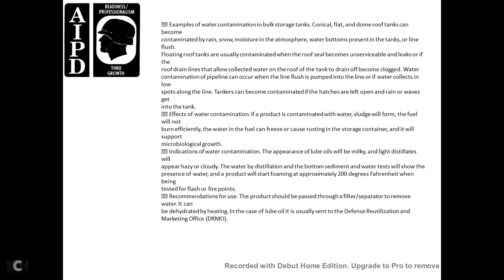Water contamination in pipelines can occur when the line is flushed and pumped with water which collects in low spots along the tank line. Tankers can be contaminated if hatches are left open to rain and waves. Effects of water contamination: product contaminated with water will form sludge, fuel will not burn efficiently, water in fuel can freeze causing rusting of storage containers, and it will support microbiological growth.